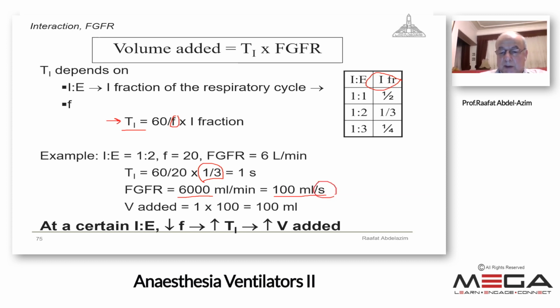So if the inspiratory time is only 1 second, the addition will be 100. If the inspiratory time is 1.5 seconds, this means that 150 will be passing into the inspiratory limb. So it depends on the inspiratory time and the flow rate. The effect of fresh gas flow depends on the fresh gas flow rate and the inspiratory time. If the fresh gas flow rate is 6 liters per minute, it will give 100 milliliter per second.